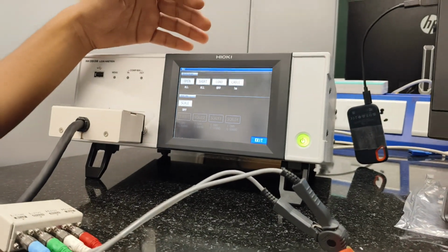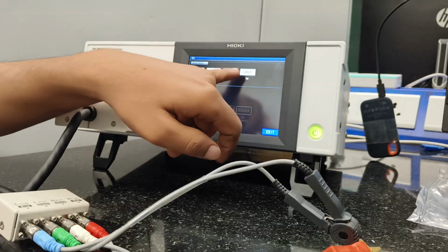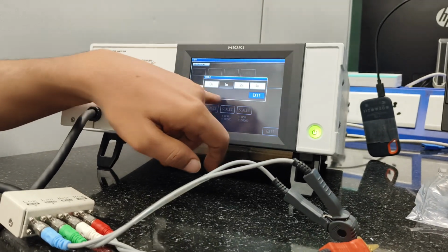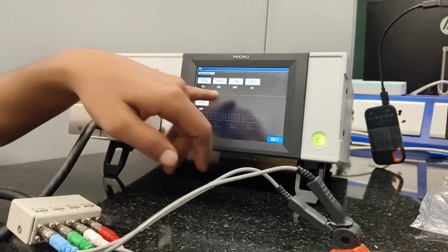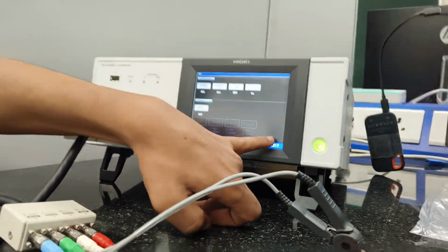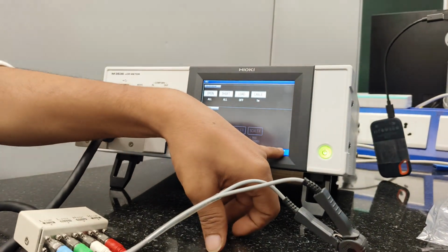So let's go in a flow. First, you need to do the adjustment if you are starting. Open, short, that's all. Cable. Yes, cable you have to give. For the cable you have to define what meter it is. Then open, then short. Then load is not required. Load compensation, right now we are not connecting a load. Okay. What is that meant for?